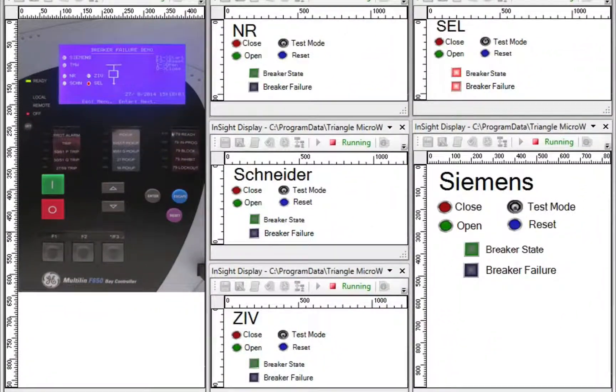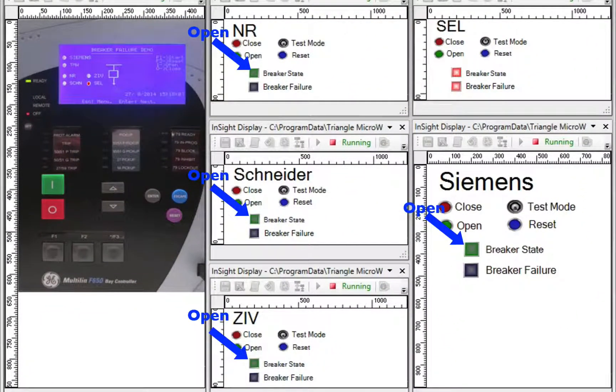Now let's take a look at the front panel displays. Notice they all show the breaker has opened except for the Schweitzer display, which shows the breaker failure status.